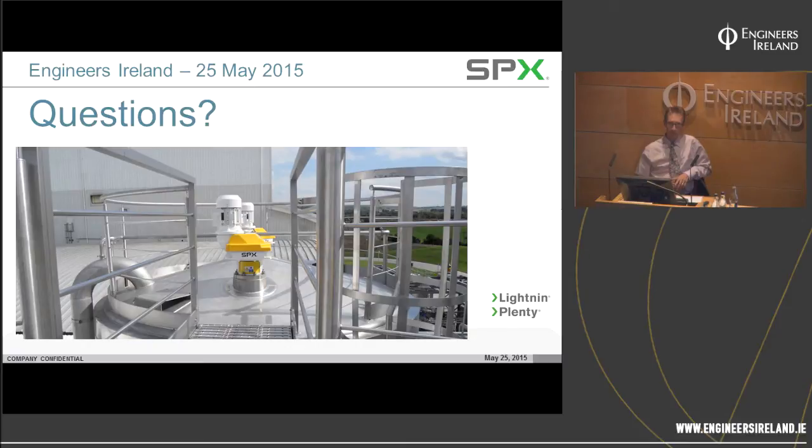The customer didn't want to be injecting strong acid or sulfuric at the top, where it was going to be essentially pushed back up. Yeah, what we normally recommend is that you inject on the suction side of the impeller within the swept diameter. That will be difficult. I guess an alternative would maybe be upstream, up at the wall. What you're trying to do is incorporate the additive within the loop.